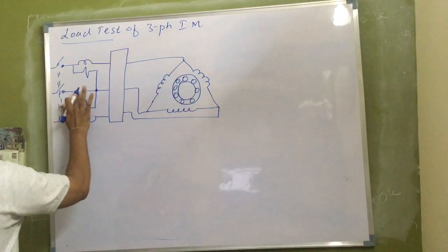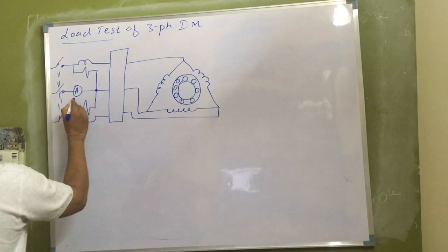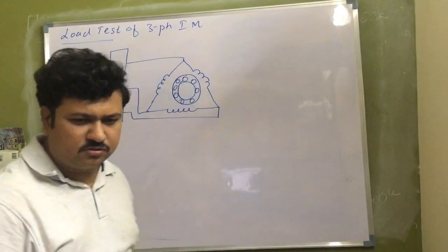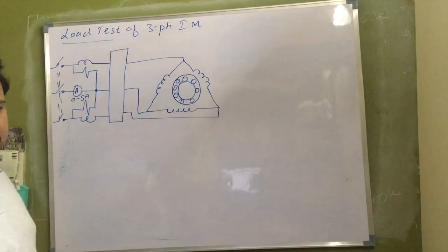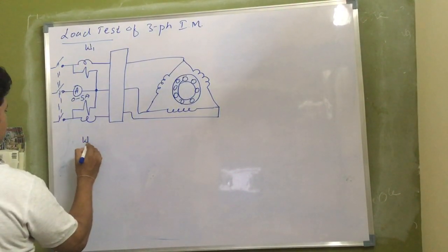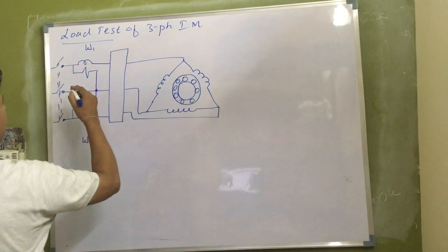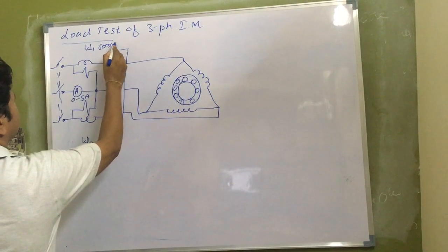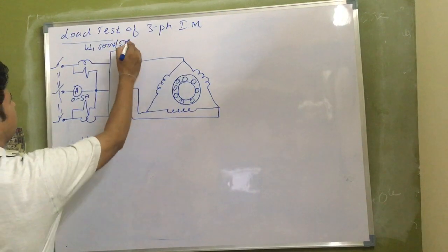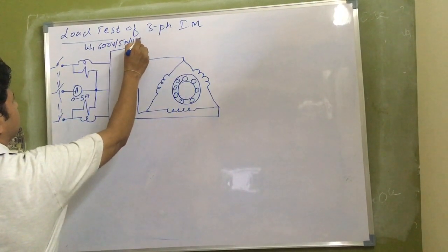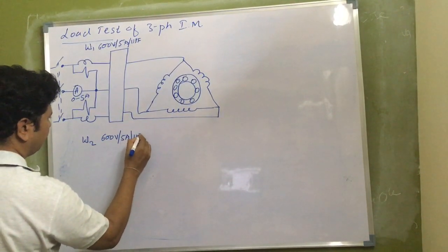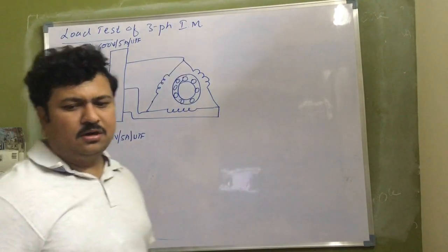So I have an ammeter here, 0 to 5 amperes, because the current rating of the motor is 4.8 amperes. So a 0 to 5 amperes ammeter is sufficient. In the circuit diagram it is shown as 10 amperes. It's fine, no issues. W1, W2. The range of wattmeters is 600 volts, 10 amperes, or generally we use 5 amperes. We don't want 10 amperes because the current rating is 4.8, UPF. Same, 600 volts, 5 amperes, UPF. This is what I need.